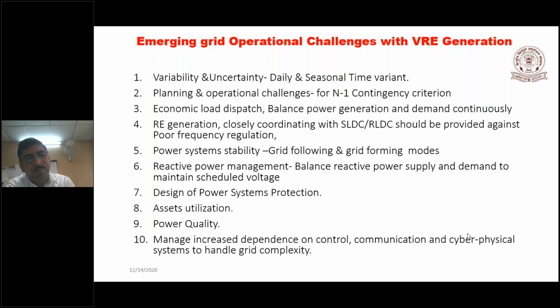But as of today, suppose I have 30% renewable and the remaining 70% coming from fossil. Those thermal powerhouses are managing the reactive power. But slowly, as the penetration of renewables keeps increasing, and our intention is to use the megawatts from solar power plants since they are eco-friendly, on the other side I don't have reactive megawatt support from these resources. So we are forcing our thermal power plants to generate the reactive power only, not the active power. The active power we are taking from the renewables; the reactive power we were taking from the thermal power plants.